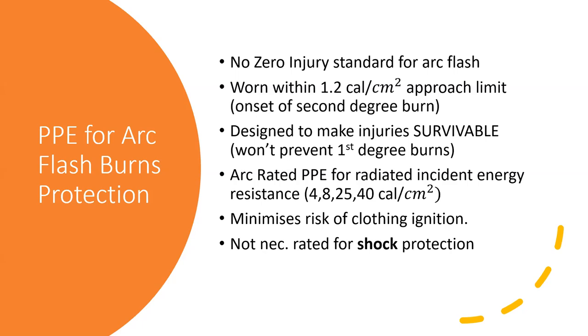Arc flash PPE is not necessarily rated for shock protection. Similarly, shock protection such as rubber gloves is definitely not rated for arc flash protection. So if you were working on high voltage equipment, you might need to wear the rubber gloves and then leather over gloves over that. Generally, ENA recommend arc flash rated PPE of 4 calories per square centimetre.